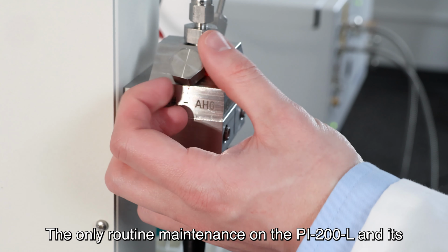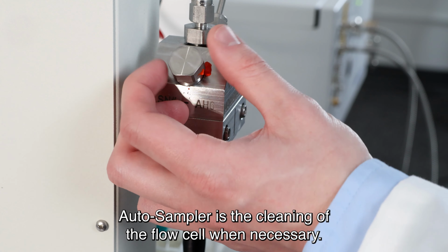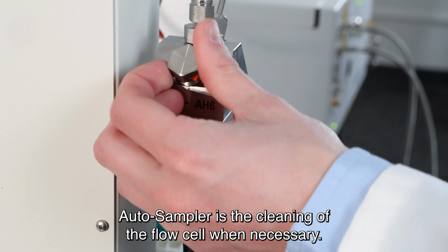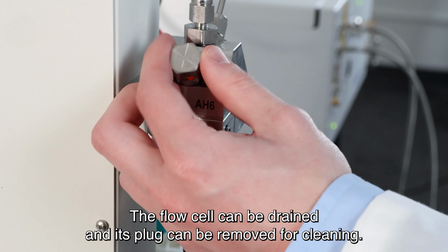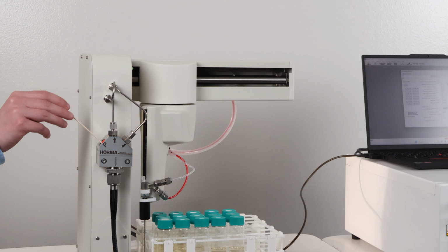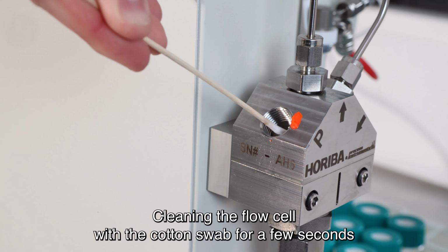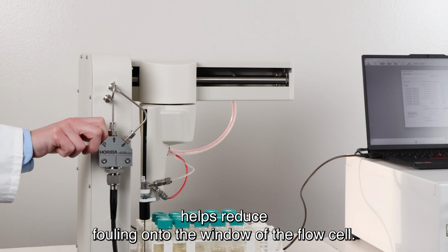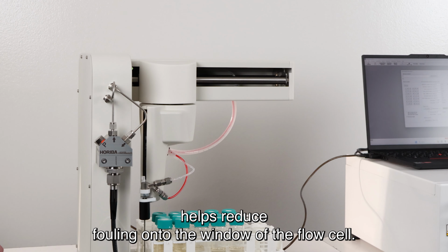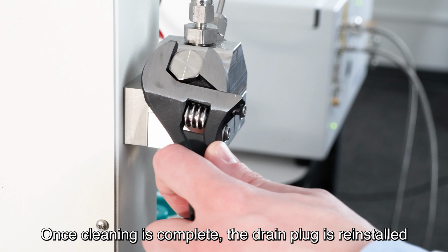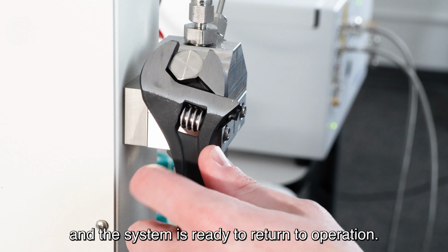The only routine maintenance on the PI-200-L and its autosampler is the cleaning of the flow cell when necessary. The flow cell can be drained and its plug can be removed for cleaning. Cleaning the flow cell with the cotton swab for a few seconds helps reduce fouling onto the window of the flow cell. Once cleaning is complete, the drain plug is reinstalled and the system is ready to return to operation.